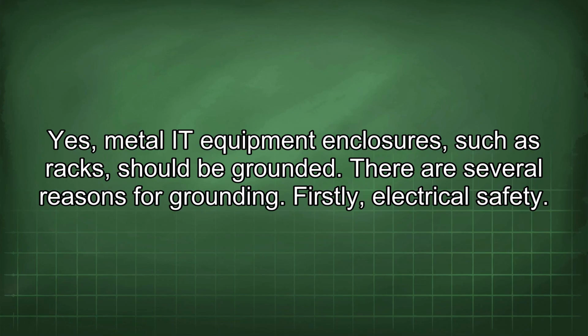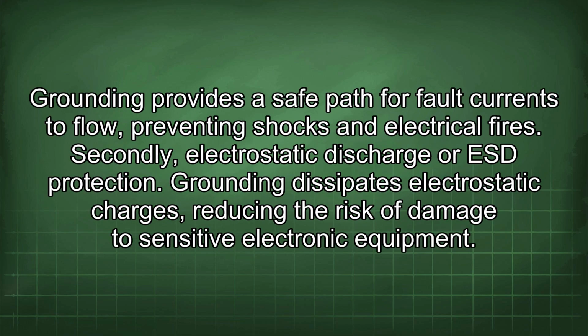Yes, metal IT equipment enclosures, such as racks, should be grounded. There are several reasons for grounding. Firstly, electrical safety. Grounding provides a safe path for fault currents to flow, preventing shocks and electrical fires. Secondly, electrostatic discharge or ESD protection. Grounding dissipates electrostatic charges, reducing the risk of damage to sensitive electronic equipment.